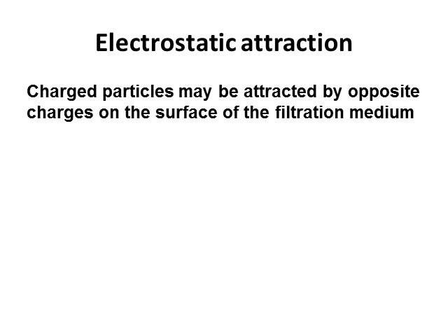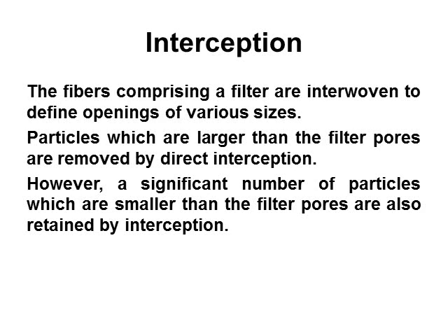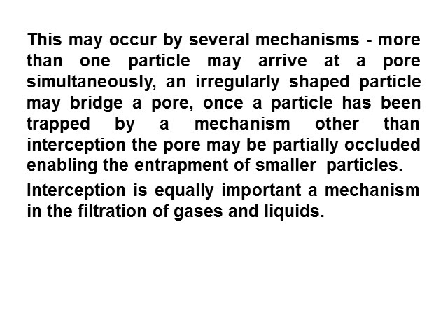Electrostatic attraction: Charged particles may be attracted by opposite charges on the surface of the filtration medium. Interception: The fibers comprising a filter are interwoven to define openings of various sizes. Particles larger than the filter pores are removed by direct interception. However, a significant number of particles smaller than the filter pores are also retained by interception through several mechanisms: more than one particle may arrive at the pore simultaneously and bridge it; or once a particle is trapped, the pore may be partially occluded, enabling entrapment of smaller particles.